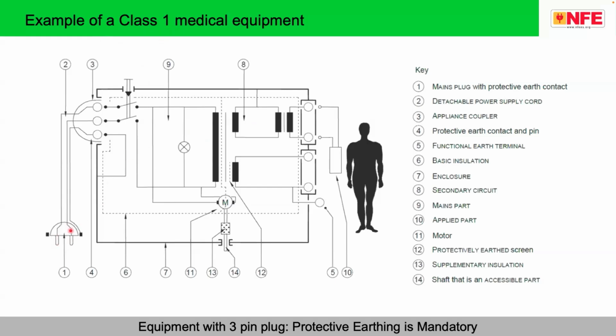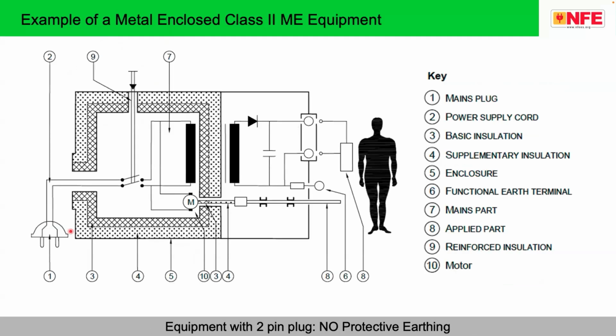Now, the classification: class 1 medical equipment is very simple to identify. These are equipment which have a 3-pin plug, 3-pin for a single phase, in the sense there is a phase, neutral, and earth pin. Class 2 equipment are generally equipment with a 2-pin plug. The device which has a 3-pin plug has one pin as the earth pin, the protective earth pin, whereas in a class 2 equipment, you don't need to have an earth pin.